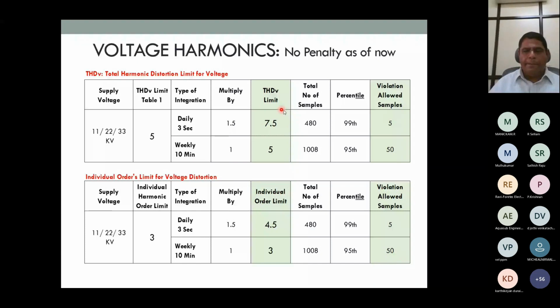Similarly, for weekly, it will be 95th percentile. The limit is 5, that is multiplication factor is 1, so the limit is 5. Total number of samples for the whole week will be 1008 samples, and out of which 50 samples can exceed this 5%. So it will be a much relaxed regulation than the older methods. It is not so strict. Earlier regulations was almost 100%. So it is practically not possible for a consumer to comply with the old regulations.